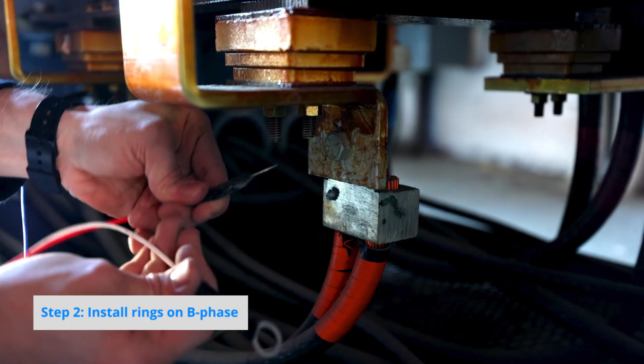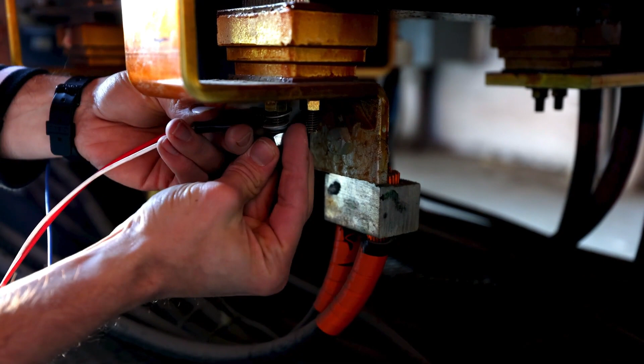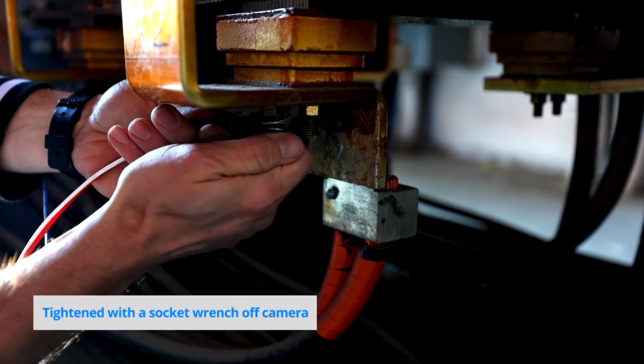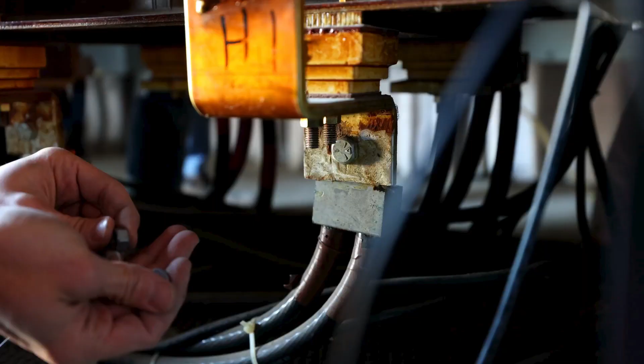Since this is a three-wire system, this transformer monitor has us hook up our neutral to B-phase as well, and then the math is done inside the monitor. So you see red and you see white. We are putting those on this lug here, lock washer and nut, so it doesn't come off. Just like C-phase, now we have B-phase done as well.